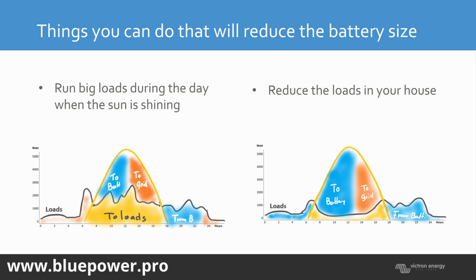And then other types of systems is with reduced loads, so there's not as many peak loads, and you can also have a smaller battery bank and smaller PV system size, and that will cover this customer's requirements. So that's basically worked out on the amount of PV you produce during the day. That sum must cover your total consumption for the household for the day. And then the battery must cover at least 60% of the household's power, 60 to 70%, so that at night from 6 until 6 again the following morning, which is not going to be optimal.